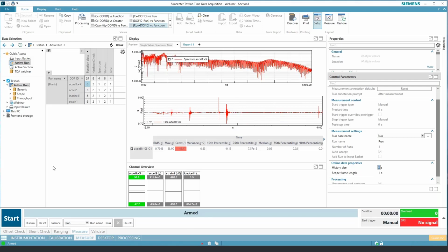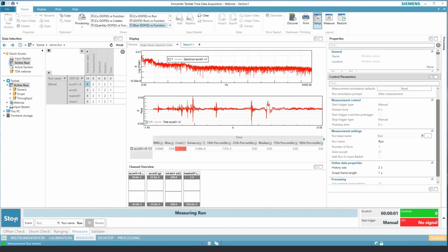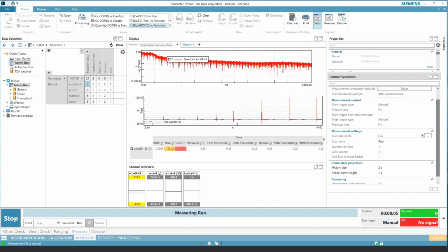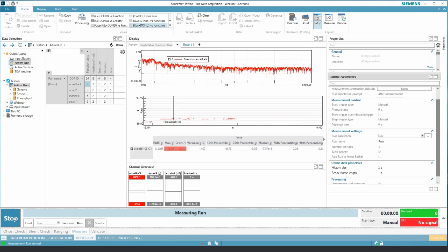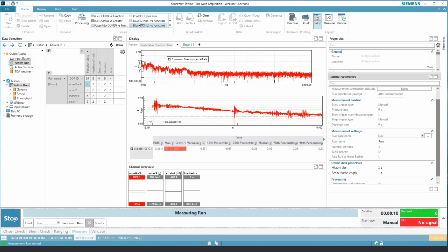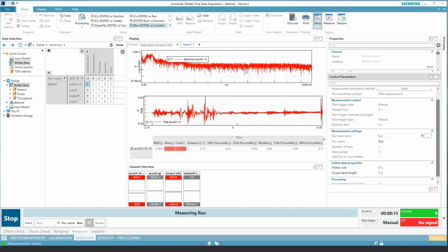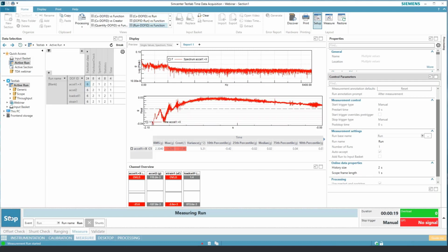All right, if I go ahead and do a start measurement, we'll just collect data on these 4 channels. I'll tap on the accel, and I want it to tap hard enough to generate an overload on the accel. I also wanted to generate a problem with my bridge conditioning module by unplugging that power supply. And then I will manually stop the measurement.